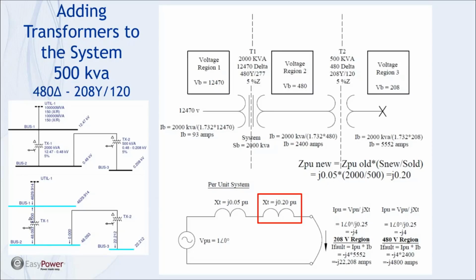So here we're going to add, I thought I'd start by adding a 500 kVA transformer in series with a 2,000 kVA. So I went back to my 2,000 kVA, 12470 to 480 with a 5% impedance, and also have the EasyPower system over here on the left. And so here's the same transformer that we had.